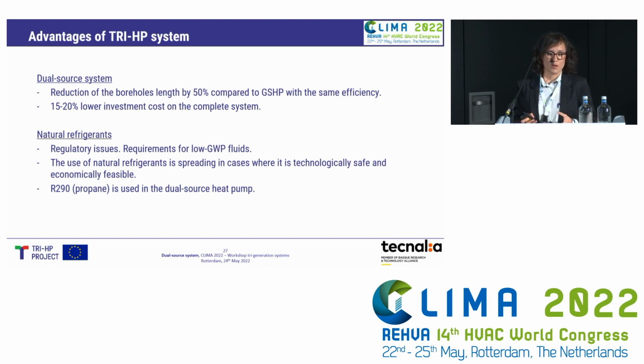These are used more and more each day due to regulatory issues such as the F-gas regulation. So we now have requirements for low global warming potential fluids, and the use of natural refrigerants is spreading in cases where it is technologically safe and economically feasible. And in this case, in the dual source system, propane is used as a refrigerant. Thanks.